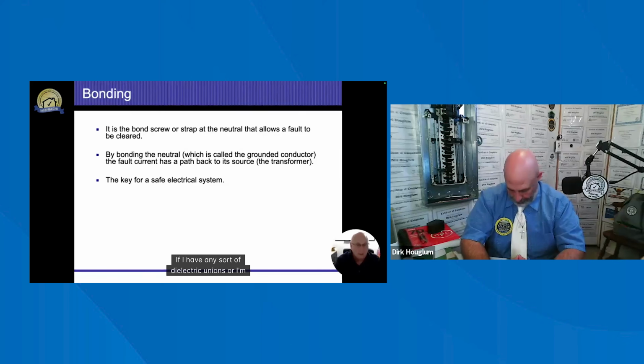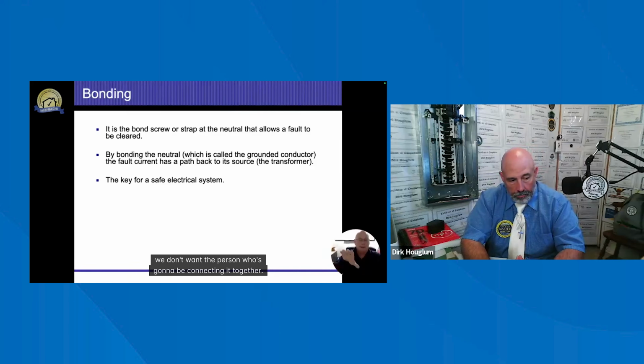If I have any sort of dielectric unions, or I'm switching to plastic pipes or something like that, I've lost my grounding connection. So I have to have jumpers over those if need be. When I get to the water meter, I want to make sure I'm jumping over the water meter as well, because there's going to be a time when the water meter might, if the house gets foreclosed and the water meter gets removed, we don't want the person who's going to be connecting it together to touch one side that's going to be 0, and then touch the water main that might be something different. Once they touch those 2 different objects, if they're different potentials, then that electricity is going to flow through them before they put it together.